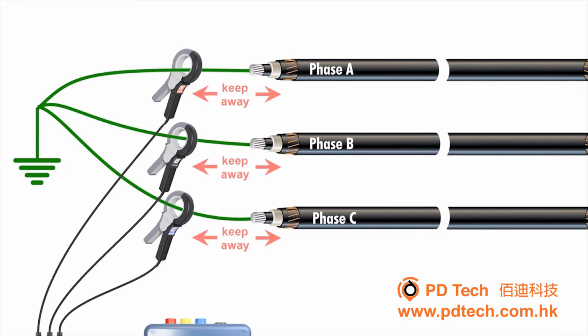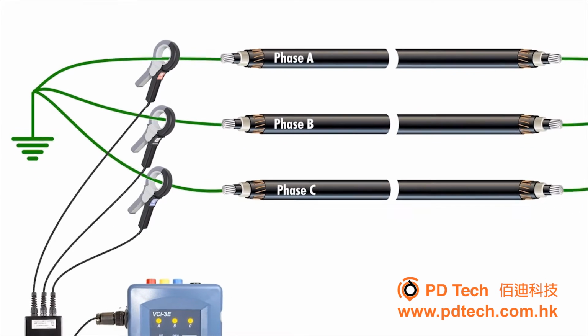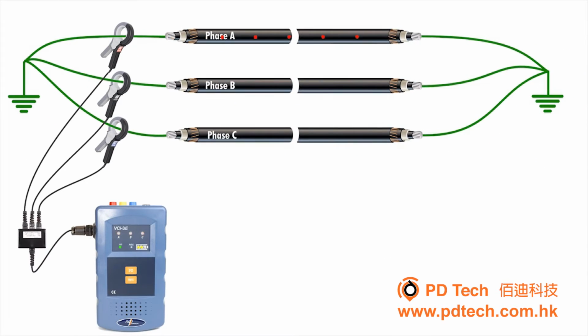It's important to keep the injection clamps away from the neutrals or shields to avoid inducing identification signals onto adjacent circuits. The VCI-3E transmitter is now sending the voice and tone identification signals throughout the conductors. This method avoids signal leakage to adjacent cables.